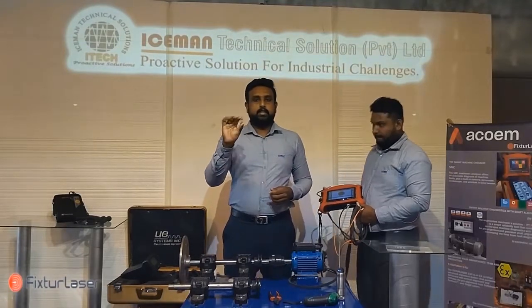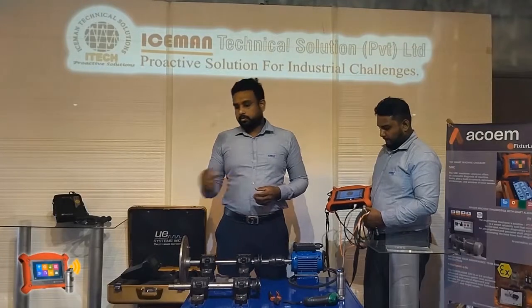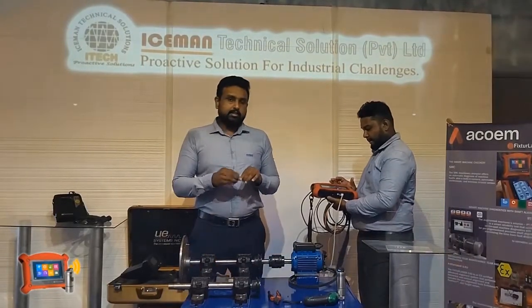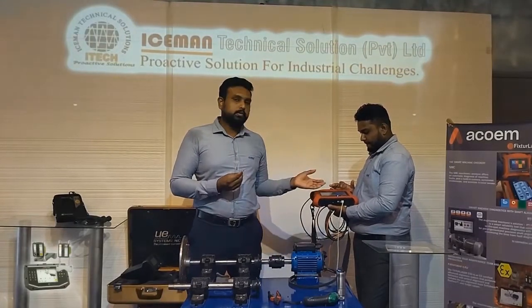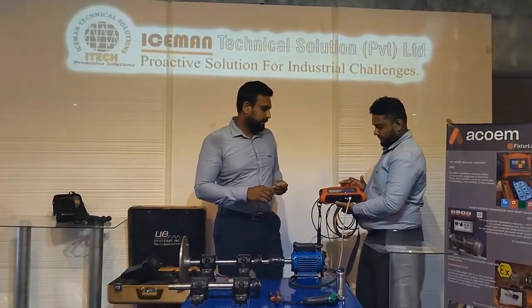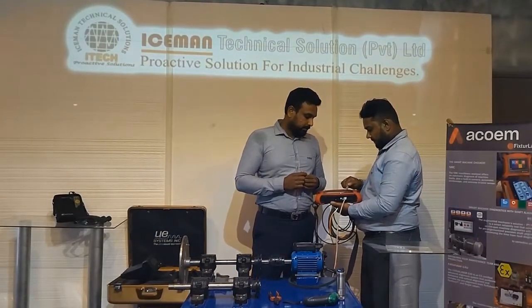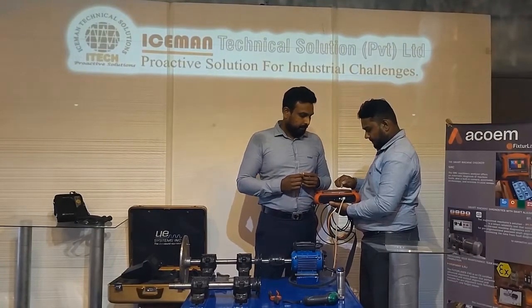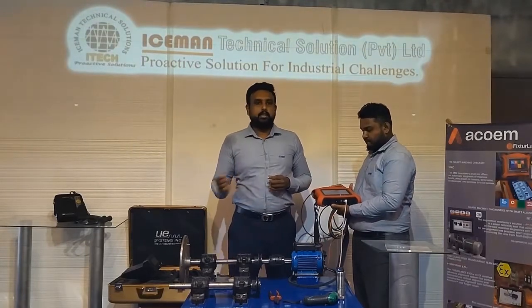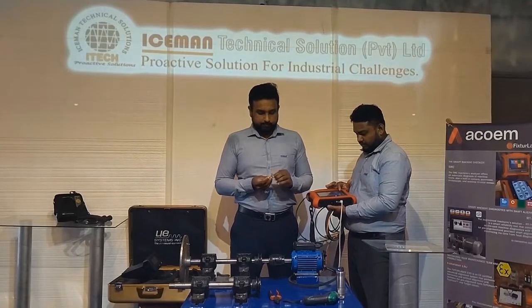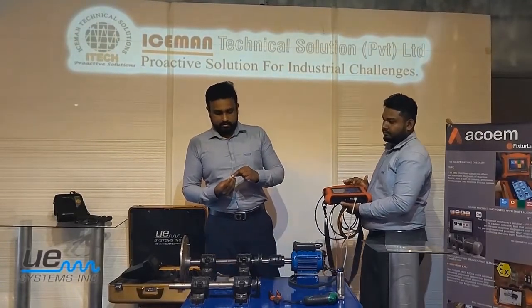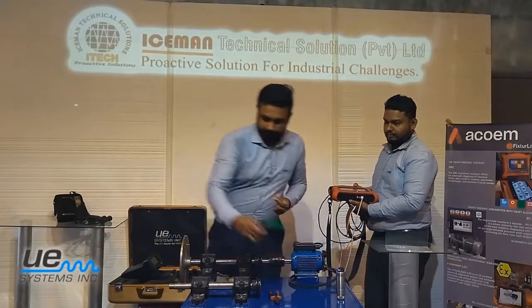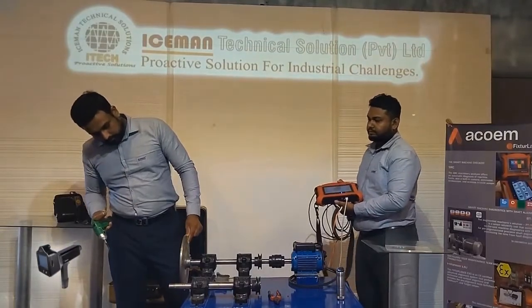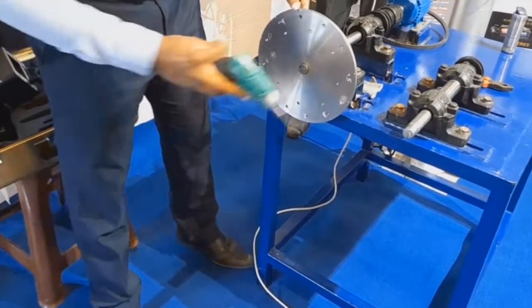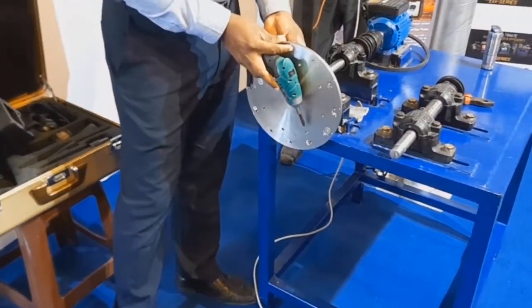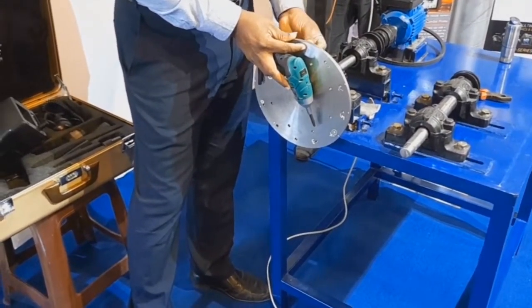Here we measured this weight, 4 grams, and we add it to the disc at a known angle, 8. This weight we want to give to our balancing module, balancing tool. So we add the known weight 4 grams and the angle is 8. This is a guess and we put it on our impeller. This is called the trial weight. We add it at position 8. 7, 8. We'll see, after adding the trial weight, how the vibration measurement varies.